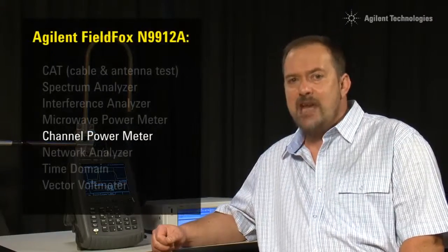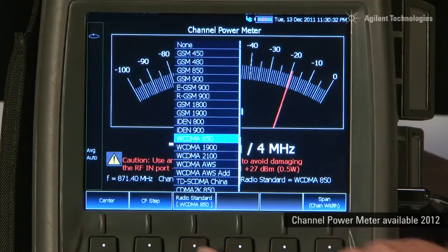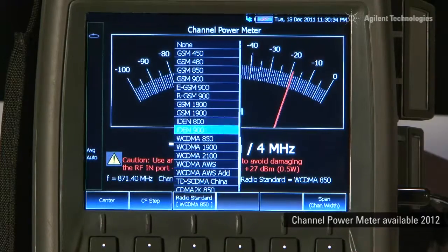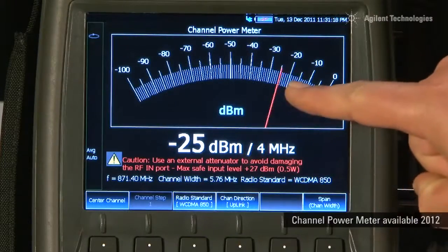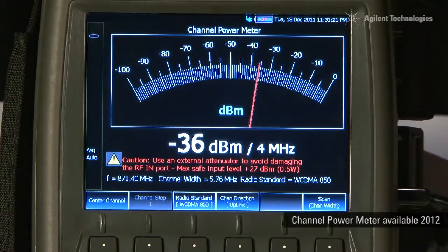And with the new channel power meter option, we can even make channelized RMS power measurements with the same traditional power meter user interface we are all familiar with, but without the need for an external power sensor.